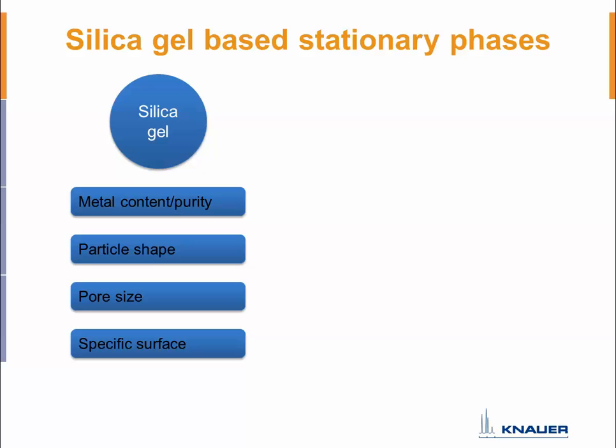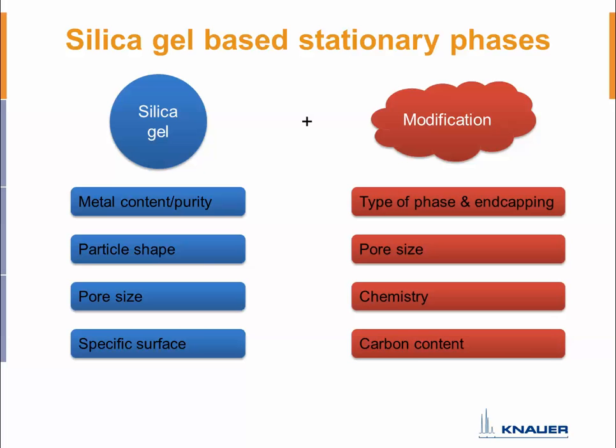But this is not everything. Most often you don't use bare silica gel but a modified one. So you also have to look at the modification — its type, the style of end capping, or whether there is an end capping at all, especially in reversed phase mode. The pore size is also affected by modification: if you bring chemistry onto the surface, the pores get smaller. For a reversed phase, the carbon content of the phase is also really important when comparing columns. All these points together define the selectivity of your stationary phase, which is why there are so many different columns on the market.